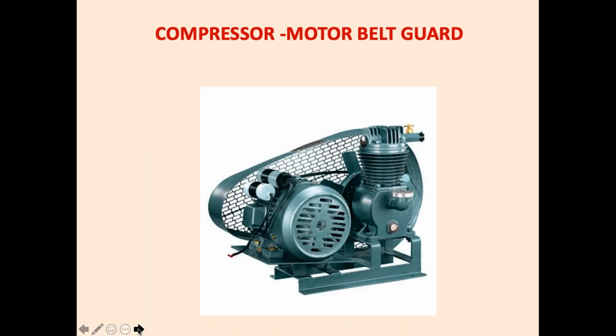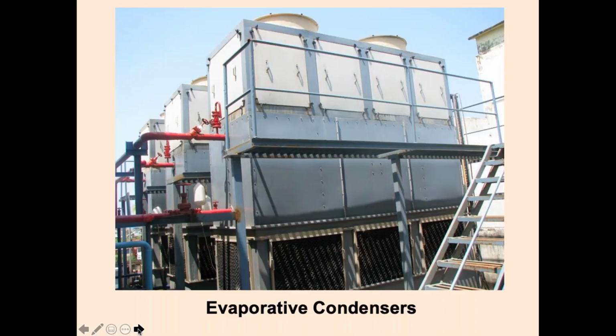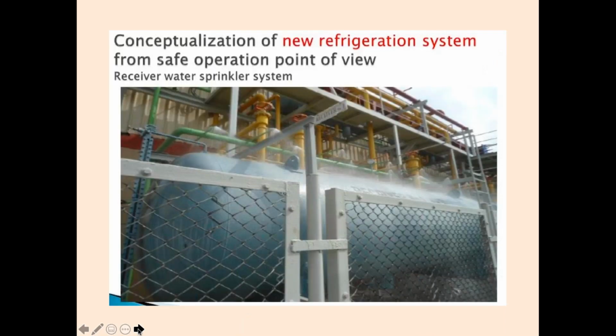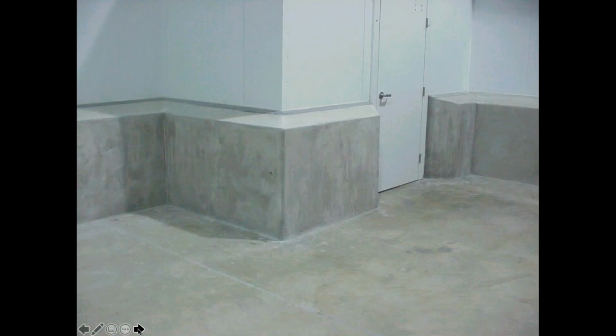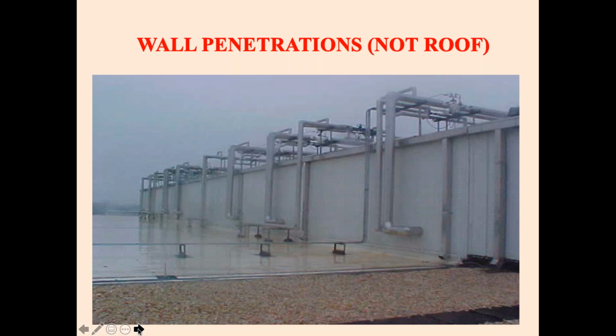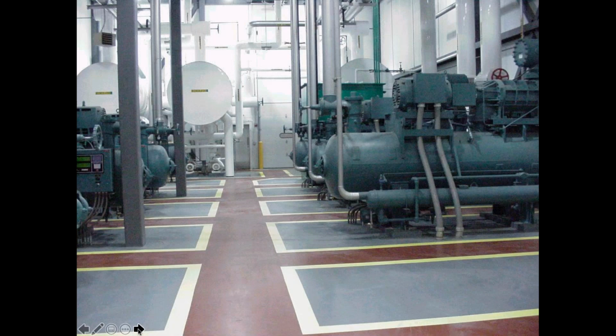Safety: always use belt guards for compressors, platforms for the evaporative condensers, then receivers, some protection. To protect the panels, build a concrete wall, otherwise your forklift trucks will damage the panels. All the connections should be taken not from the top, but from the side walls of the evaporative condensers, because otherwise drain water or rain water will go inside. This is a good machine room, plant room.